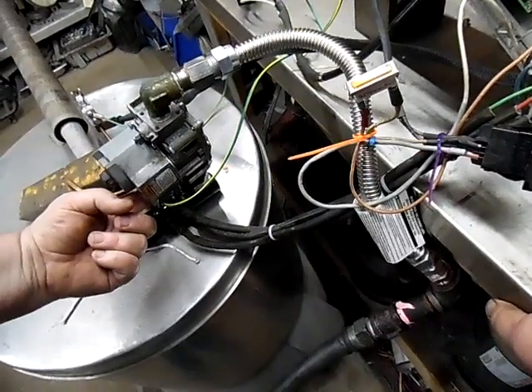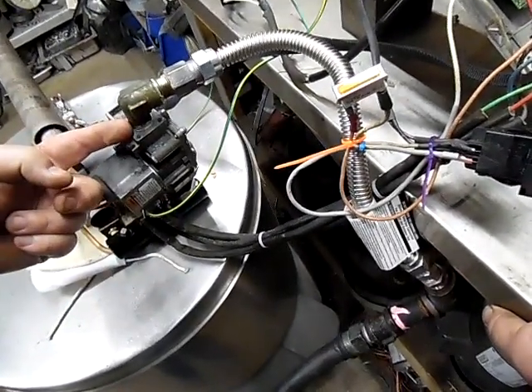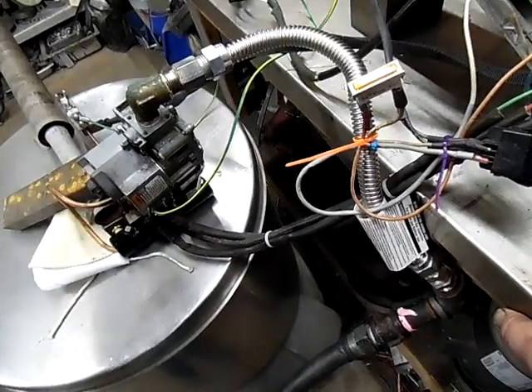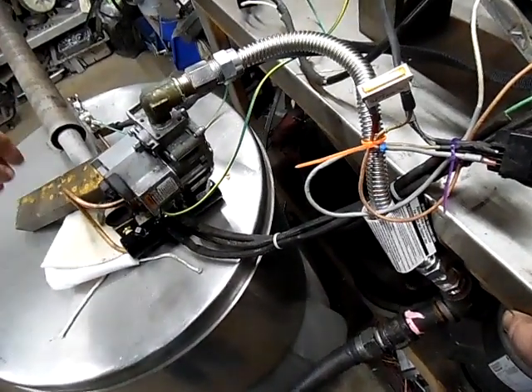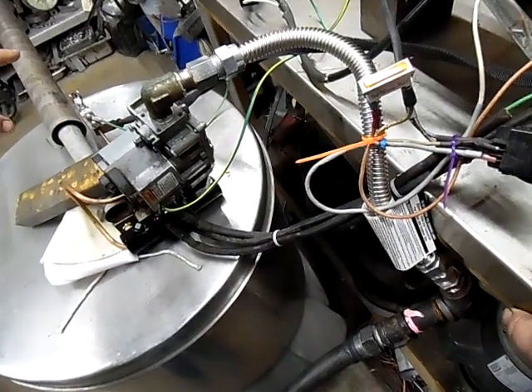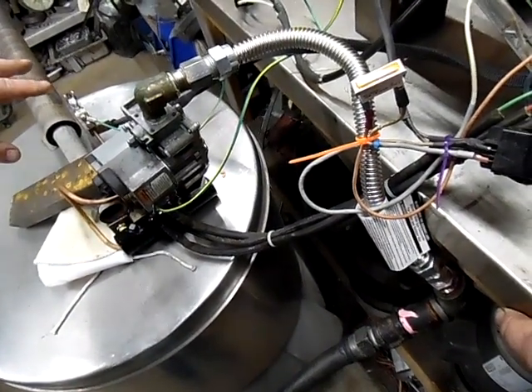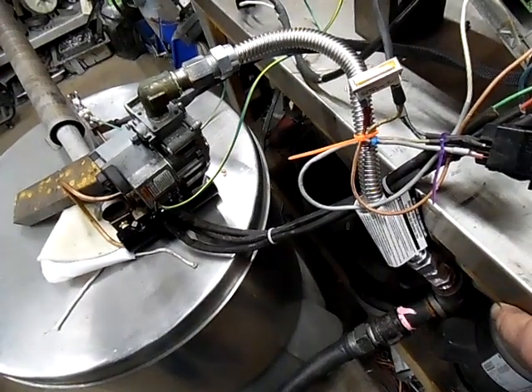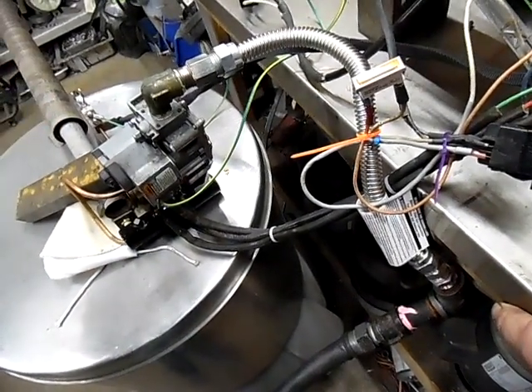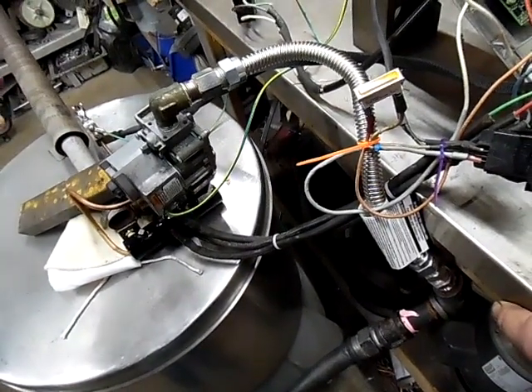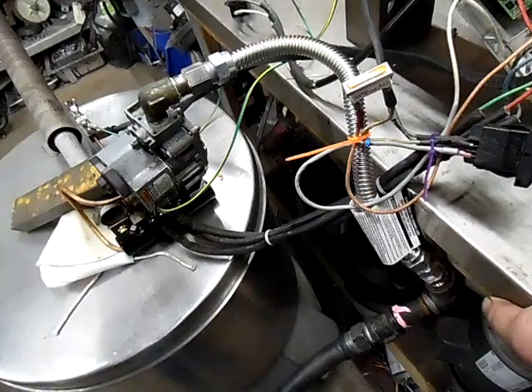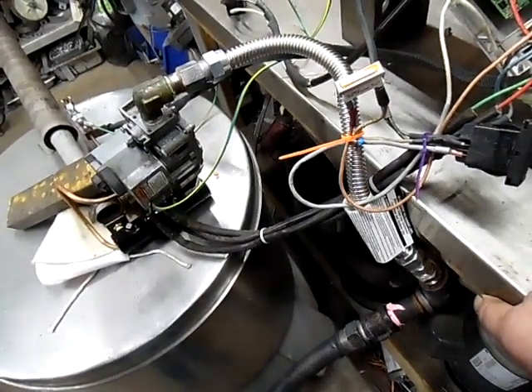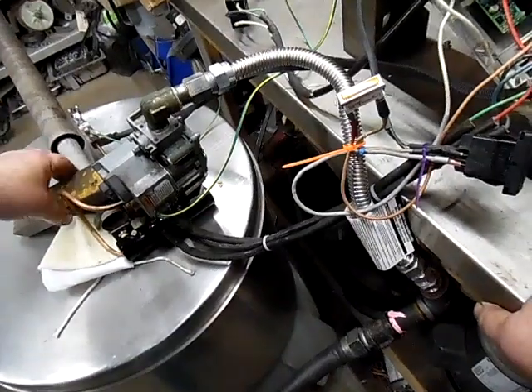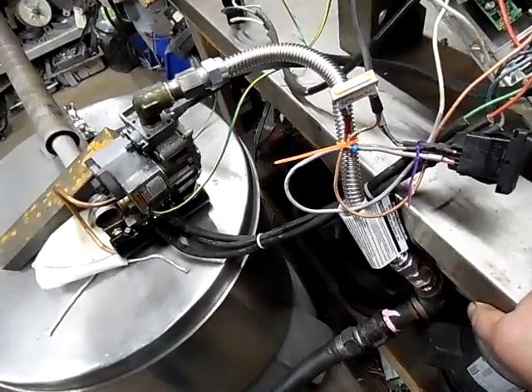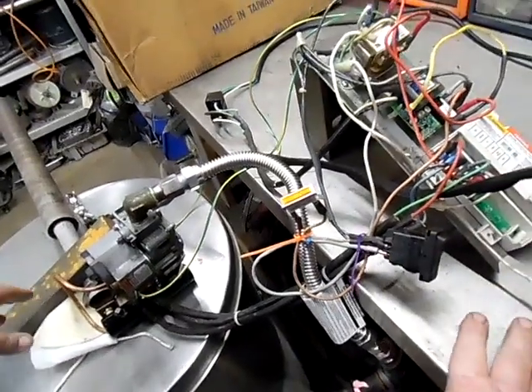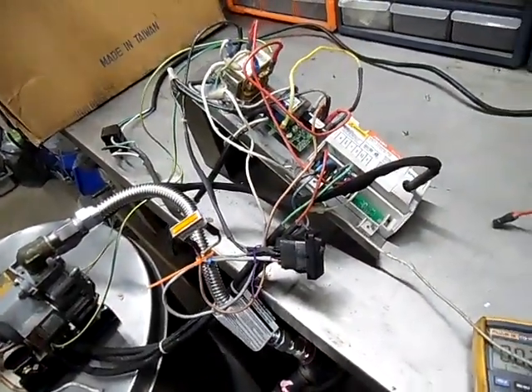So your gas repair guy should have a manometer, which he can hook into these ports. In the future, they also should be running gas analyzers, because just like your automobile, the amount of carbon monoxide increases when the burn isn't as good. And even though it will burn fine, you could modify the jets a little bit and get a better flame. It's just kind of like looking at your grill. When it works the best, you see the nice pretty blue flame. But if you run a gas analyzer, it'll actually tell you if you're burning the most efficiently, just like your car. If you're not, you're risking getting exposed to carbon monoxide, actually causing yourself injury or death. All your buildings should have carbon monoxide testers in them if you run a restaurant or a facility using gas.